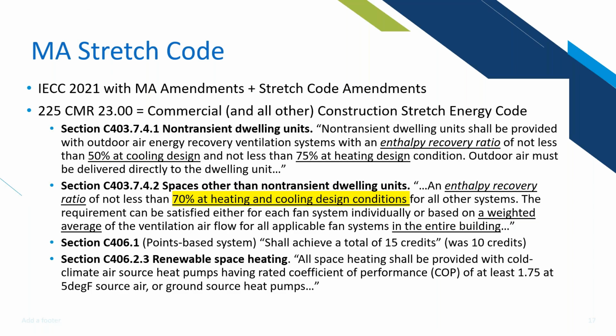But for the most part, the biggest changes to DOAS and ERV equipment is this slide right here, which talks about how now we need the 70% enthalpy recovery ratio in both heating and cooling design conditions. And it's important to note that that's a weighted average for the entire building. So that's why when we talk about high effectiveness DOAS options that we have, it could be a good way to average out that enthalpy recovery ratio of the whole building above the 70% requirement.